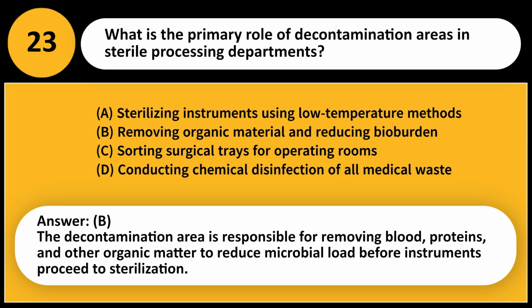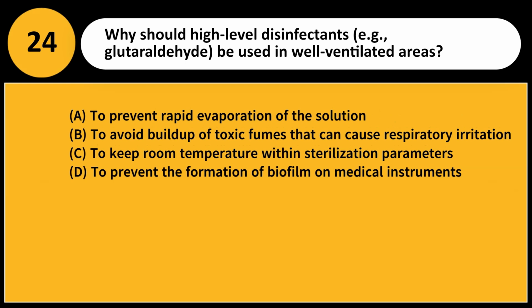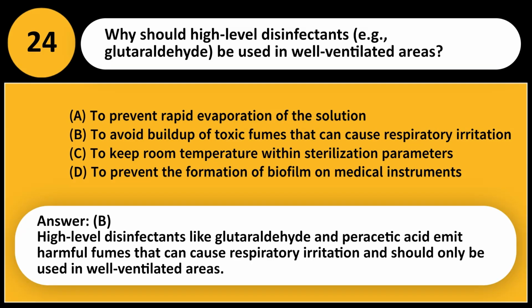The decontamination area is responsible for removing blood, proteins, and other organic matter to reduce microbial load before instruments proceed to sterilization. Why should high-level disinfectants, e.g., glutaraldehyde, be used in well-ventilated areas? A. To prevent rapid evaporation of the solution. B. To avoid buildup of toxic fumes that can cause respiratory irritation. C. To keep room temperature within sterilization parameters. D. To prevent the formation of biofilm on medical instruments. Answer: B. High-level disinfectants like glutaraldehyde and peracetic acid emit harmful fumes that can cause respiratory irritation and should only be used in well-ventilated areas.